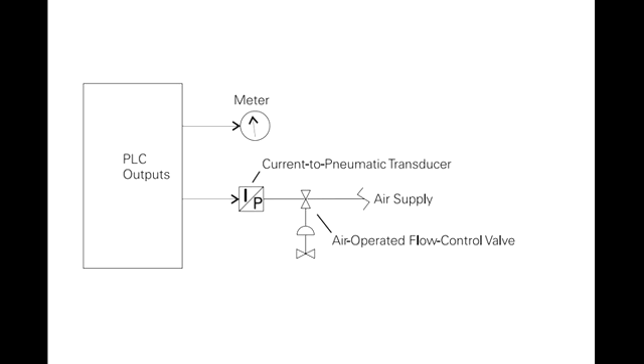Analog outputs. An analog output is an output signal that has a continuous signal. The output may be as simple as a 0 to 10 VDC level that drives an analog meter. Examples of analog meter outputs are speed, weight, and temperature. The output signal may also be used on more complex applications such as a current to pneumatic transducer that controls an air-operated flow control valve.